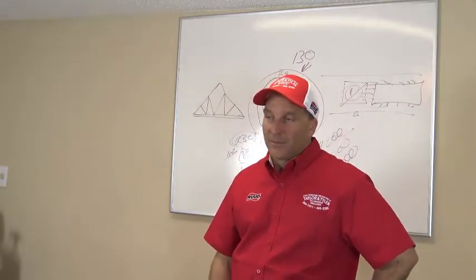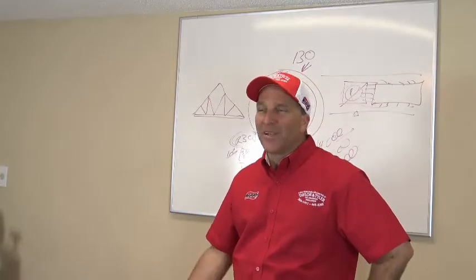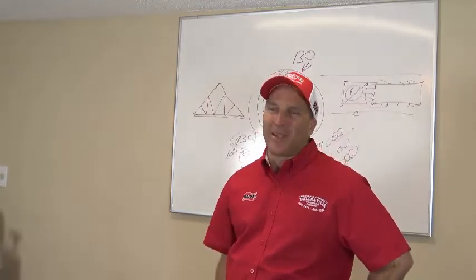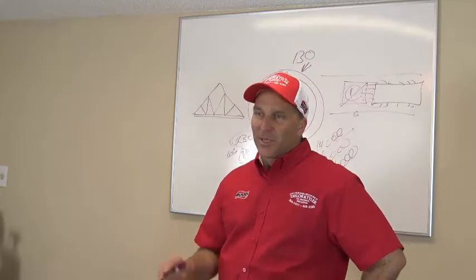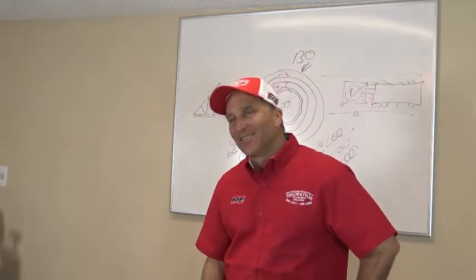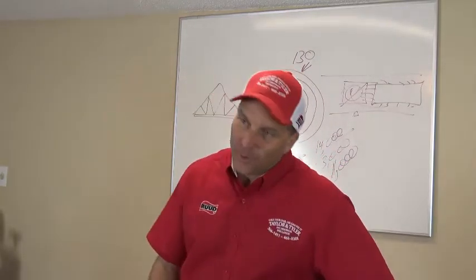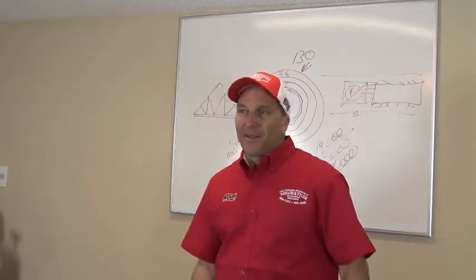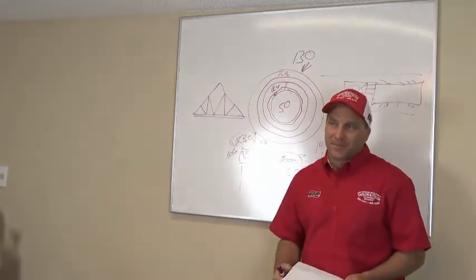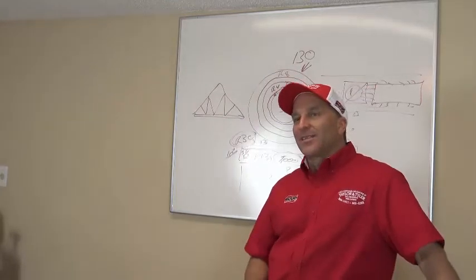He goes, it's the blower wheel. I said, what do you mean it's the blower wheel, man? The blower wheel don't make any noise. Yeah, it does when the hub's loose from it. So now I had to pull the motor out, put the old motor back in, and then get him the blower wheel the next day. Okay? So you got to know what that sound is.